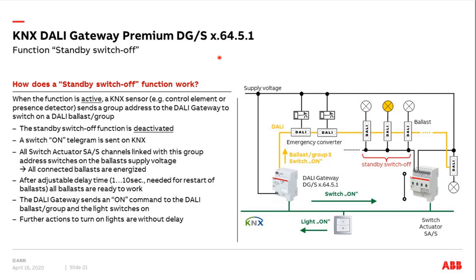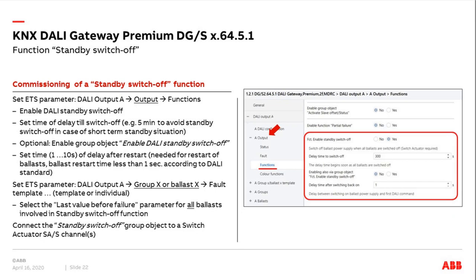It is recommended — for example when using DALI ballasts with an additional 12V or 24V power supply — to use a parameter value of two or three seconds, because the power supply may need a little more than one second to stabilize the output.